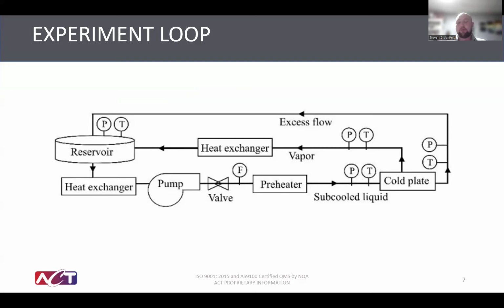But the inlet temperature is very important because that's what allows us to control the degree of subcooling, which is very important in any refrigerant testing and any evaporator testing. So that was our main experiment loop.